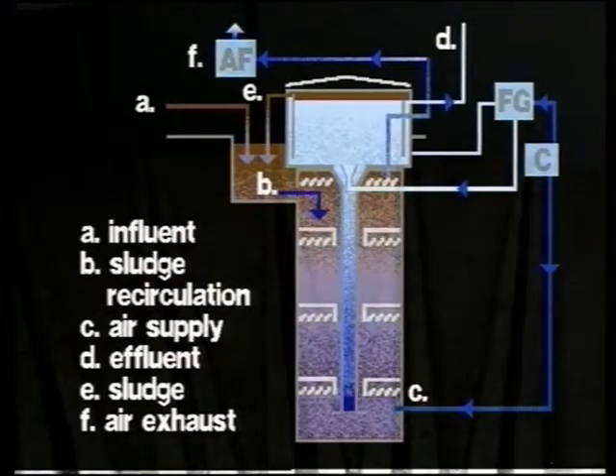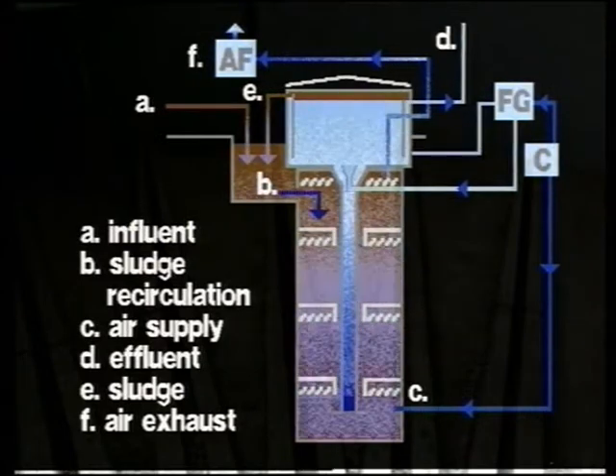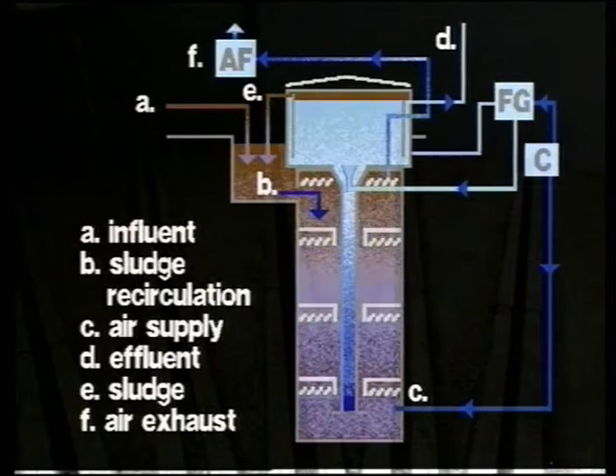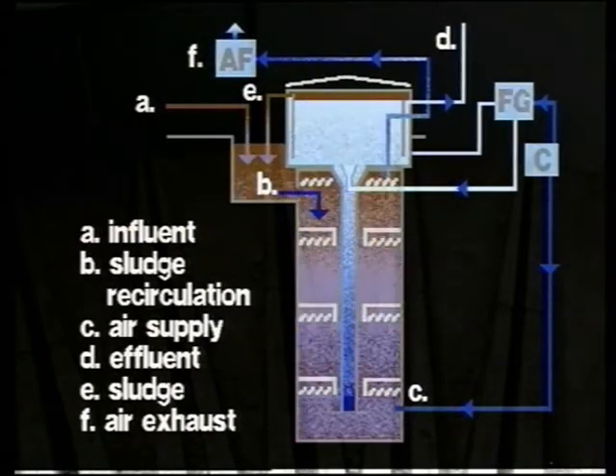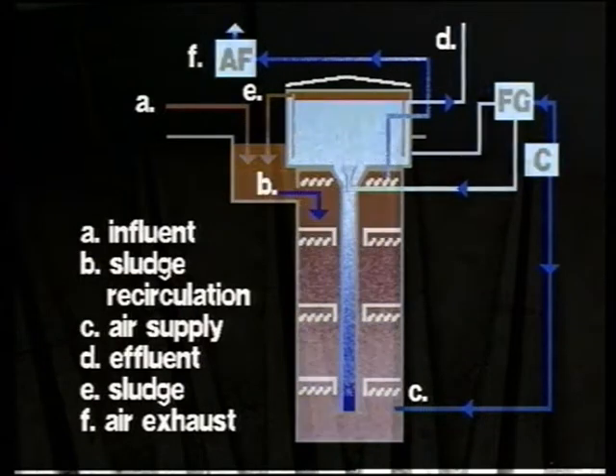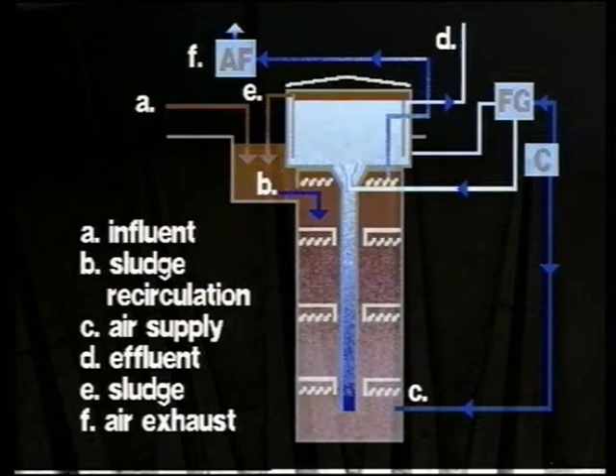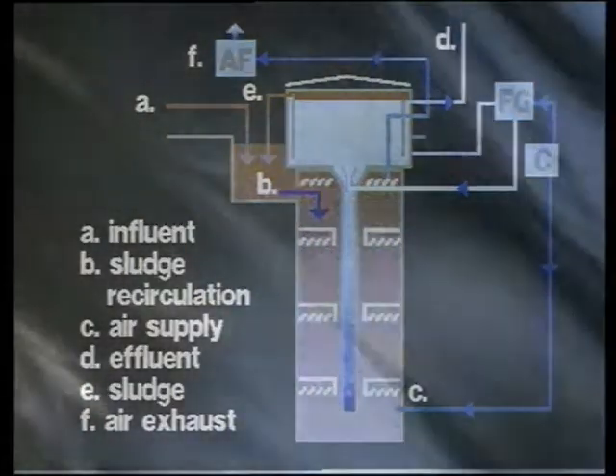Mixed water and sludge rises in the riser pipe in the center of the shaft to the flotation unit and adheres to the existing microscopic air bubbles. Beneath the flotation unit, a secondary airstream is injected via the flotation generator, which assists in increasing the process, and the floating layer of sludge is kept constantly skimmed.